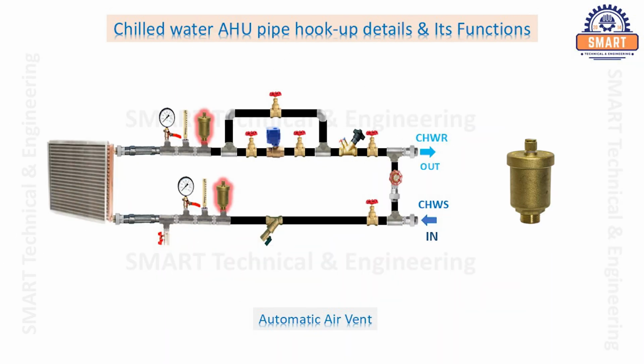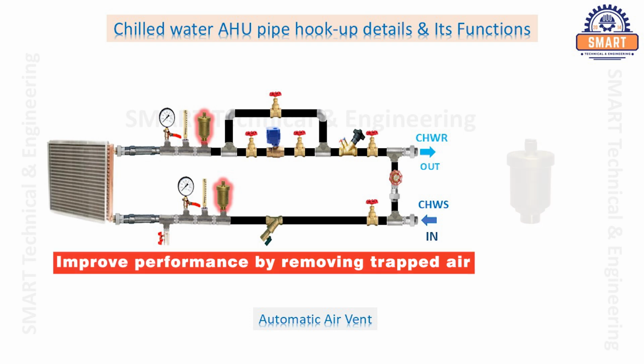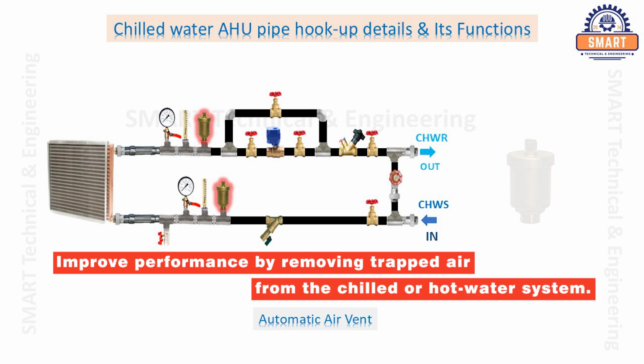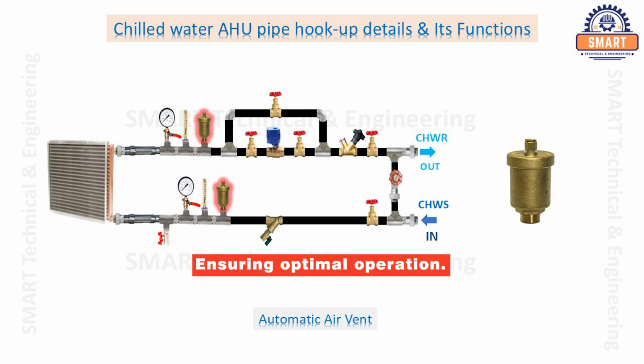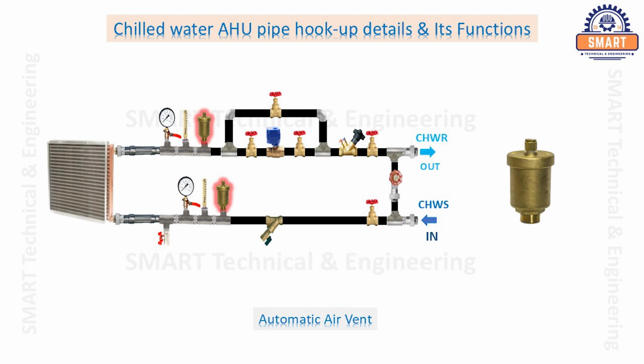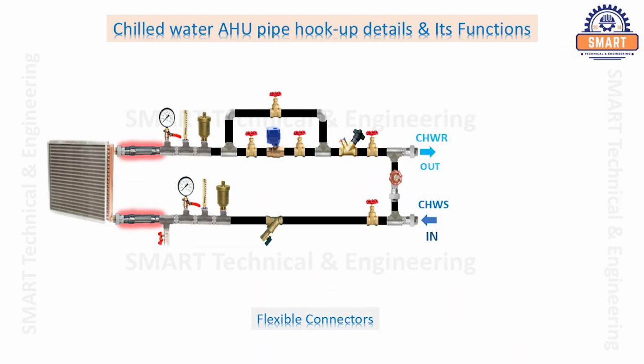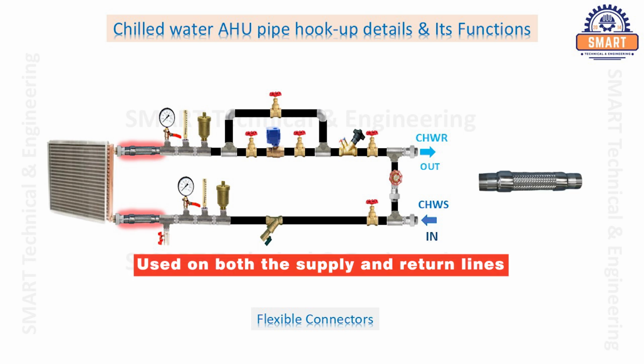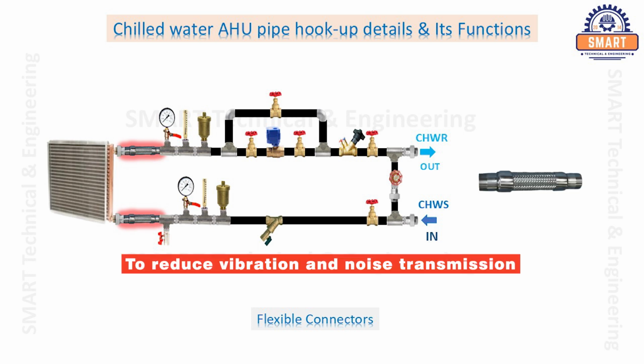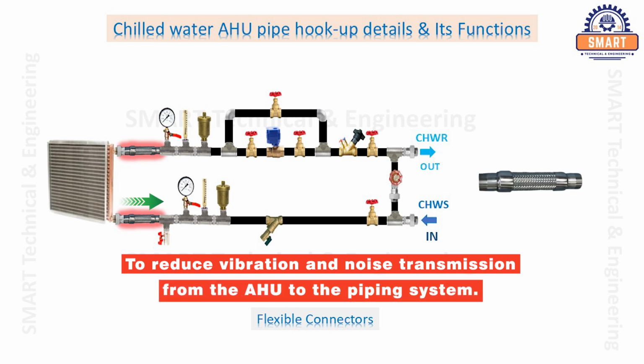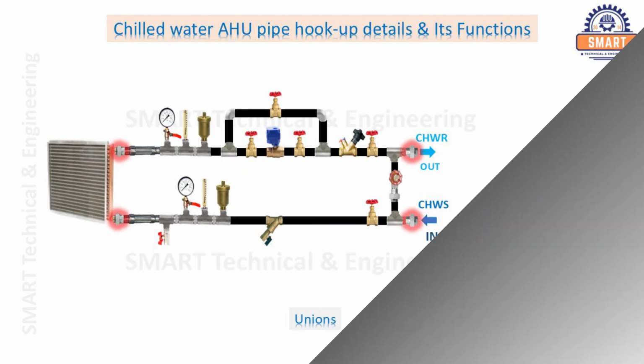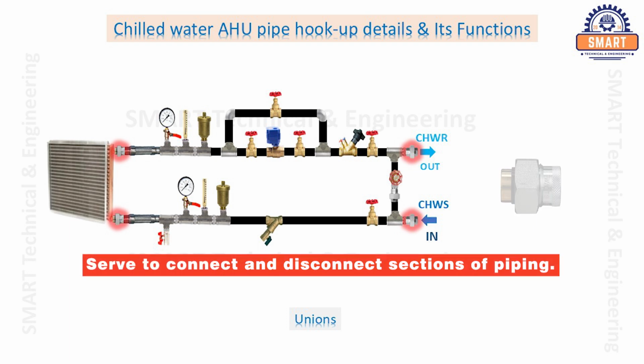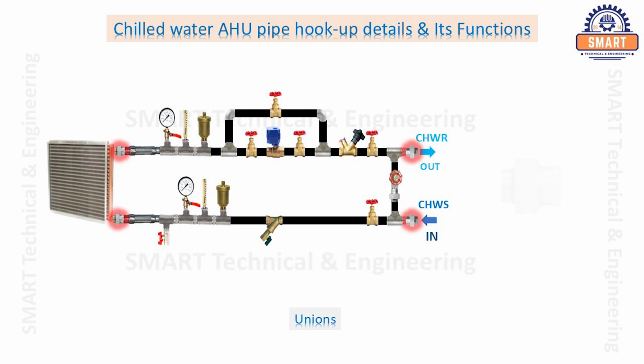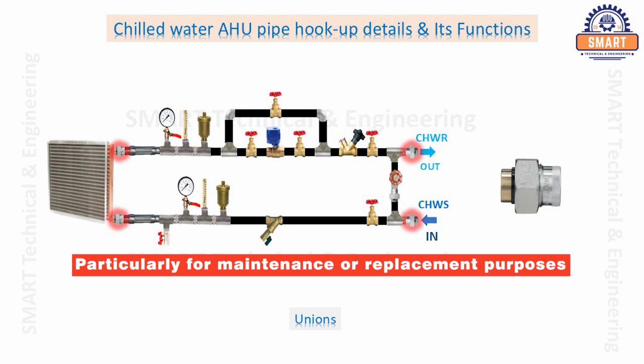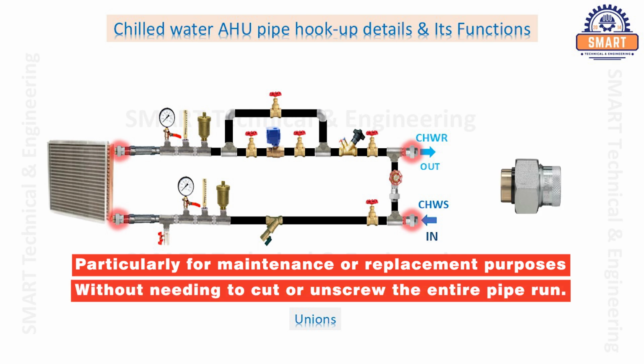Automatic air vent. An automatic air vent in an air handling unit (AHU) is vital for improving performance by removing trapped air from the chilled or hot water system, ensuring optimal operation and enhancing HVAC efficiency. Flexible connectors. These are used on both the supply and return lines to reduce vibration and noise transmission from the AHU to the piping system. Unions. These fittings serve to connect and disconnect sections of piping, particularly for maintenance or replacement purposes, without needing to cut or unscrew the entire pipe run.